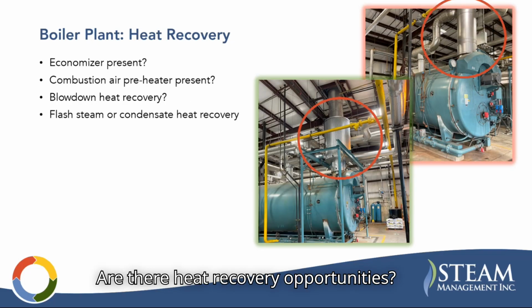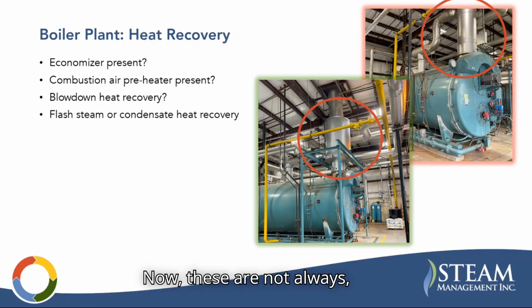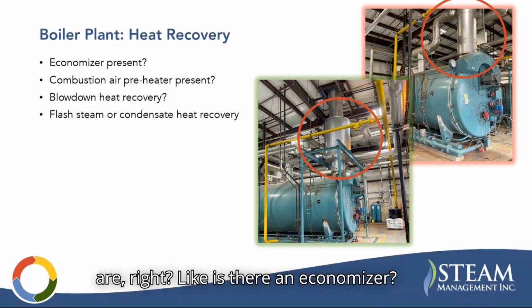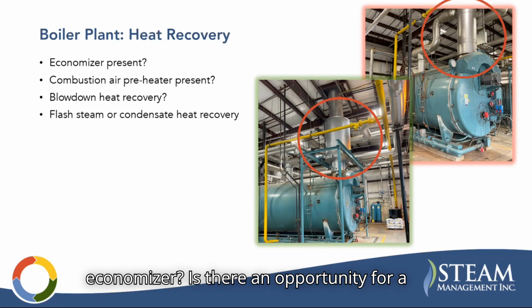Are there heat recovery opportunities? Now, these are not always attractive. This is where the inputs to the system equation can vary how attractive these opportunities are. Is there an economizer? Is there an opportunity for an economizer? Is there an opportunity for a combustion air preheater, or blowdown heat recovery?